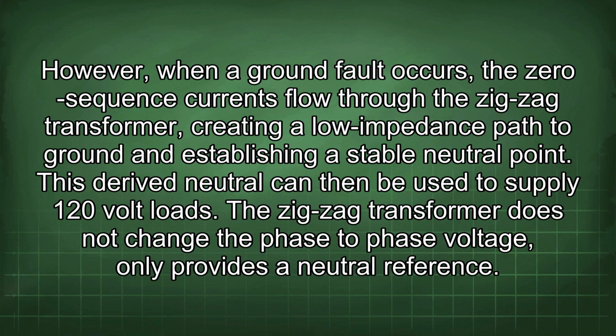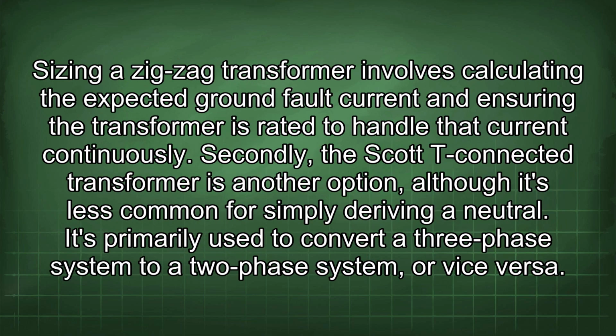However, when a ground fault occurs, the zero sequence currents flow through the zigzag transformer, creating a low impedance path to ground and establishing a stable neutral point. This derived neutral can then be used to supply 120 volt loads. The zigzag transformer does not change the phase-to-phase voltage, only provides a neutral reference. Sizing a zigzag transformer involves calculating the expected ground fault current and ensuring the transformer is rated to handle that current continuously.